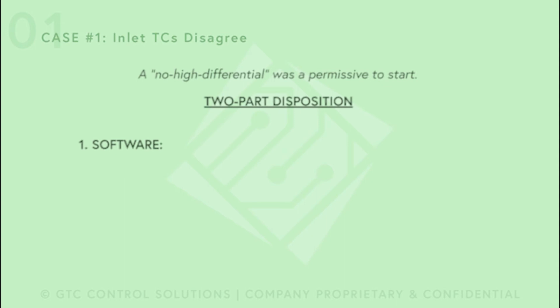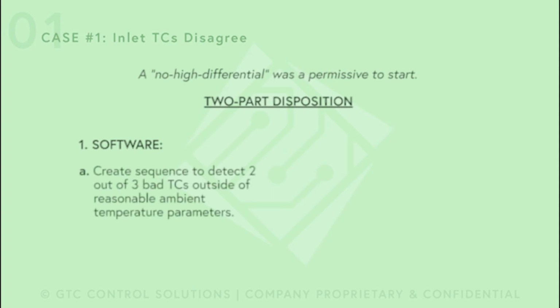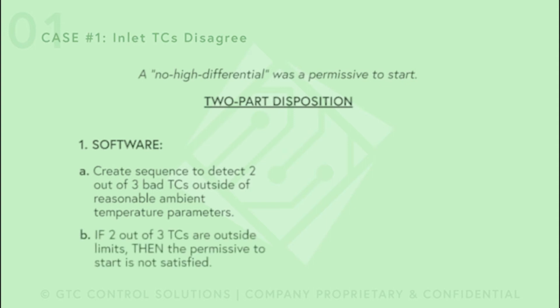And we create those detections for each thermocouple, and then a sequence that says, okay, if 2 out of 3 are okay, they're not reading crazy ambient temperatures, then that means we have a good value for the ambient temperature, we do not have a high differential, and we can start the unit. If 2 out of 3 thermocouples are outside the limits, then the permissive to start is not satisfied, because now the control system is saying, wait, 2 of your inlet thermocouples are not reading correctly. You cannot start the unit in this condition because this is a critical parameter for your DLN calculations. So with a very simple software modification, we solved the problem.